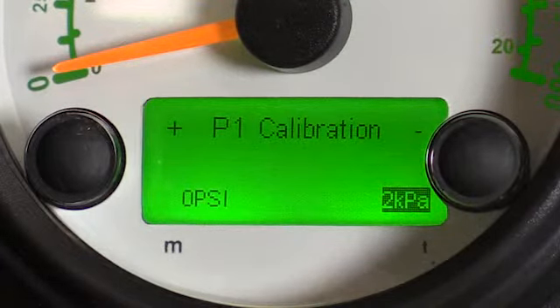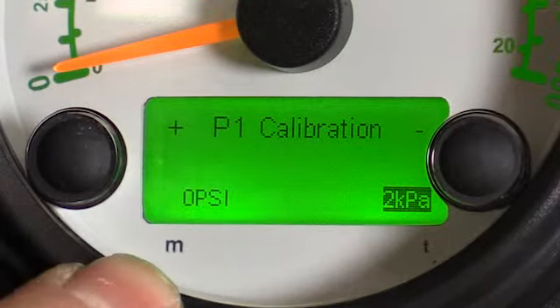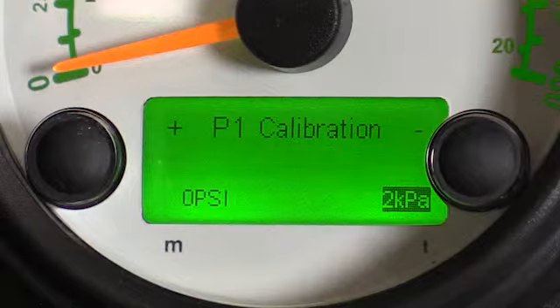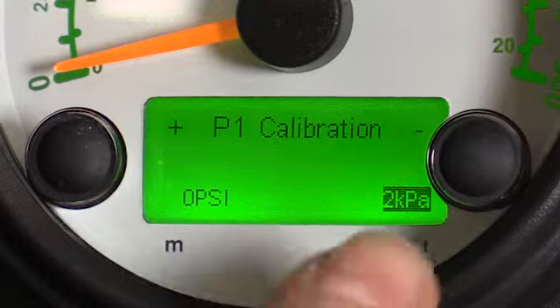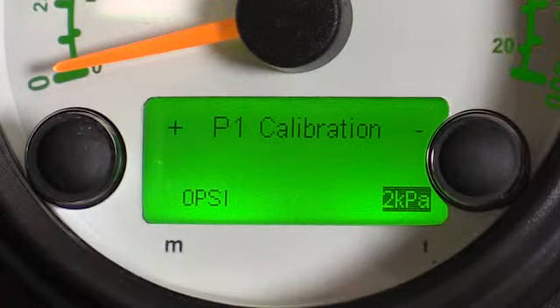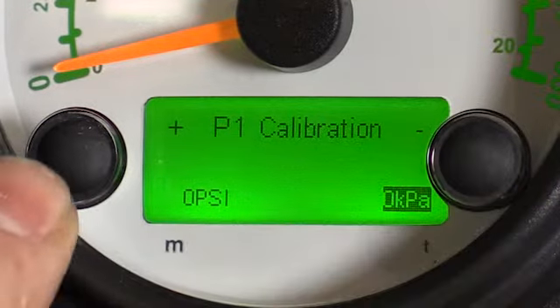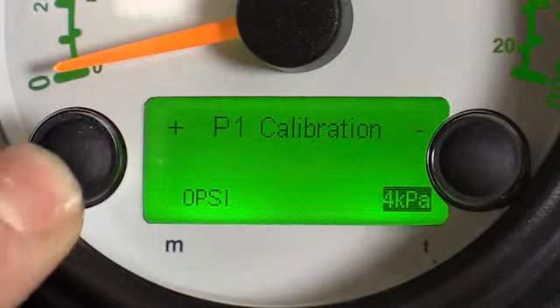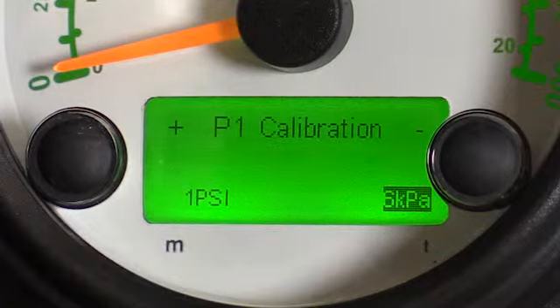We are now on the calibration screen. To change your setting, you use the M or the T button to change the number on your right. The goal is to get the number on the left to read 0 psi.